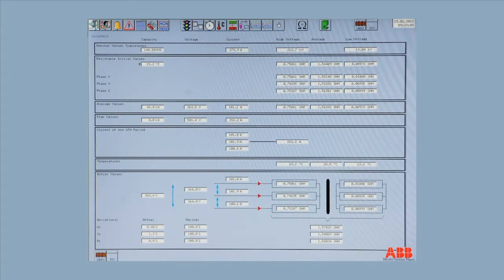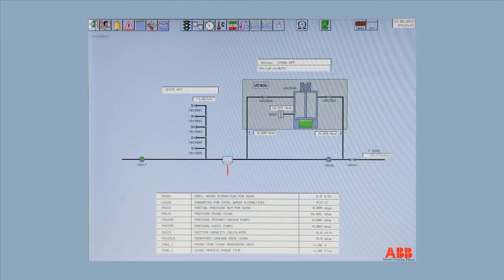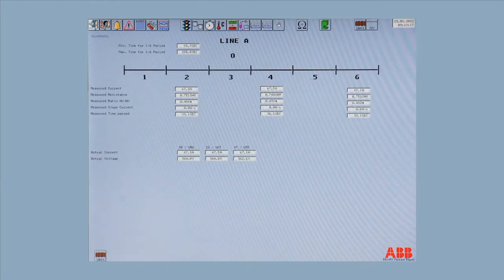This is an important screen, as it displays the resistance measurements taken during the measurement step. These values are used to relate the resistance to the temperature of the windings at any point in time during the process. The status of the VZ406 water measuring system and the VZ475 suction calibration can be checked on this screen page. The heating cycle values can be followed and viewed in real time on this screen.